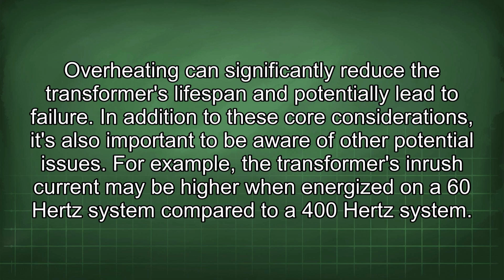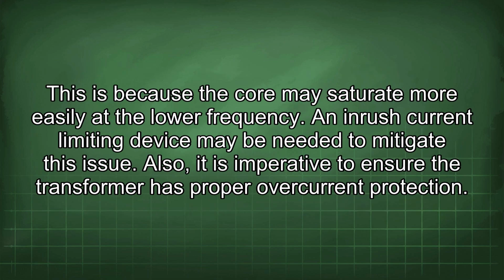In addition to these core considerations, it's also important to be aware of other potential issues. For example, the transformer's inrush current may be higher when energized on a 60 Hz system compared to a 400 Hz system. This is because the core may saturate more easily at the lower frequency. An inrush current limiting device may be needed to mitigate this issue.